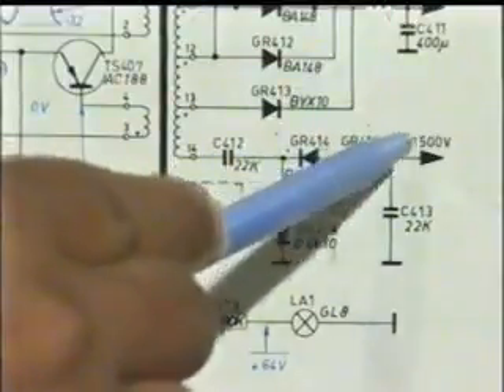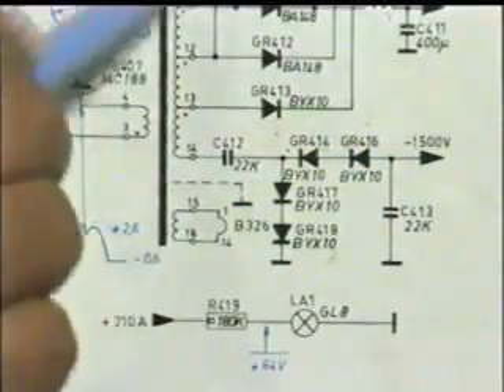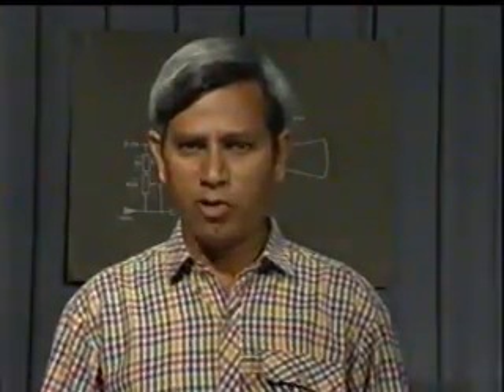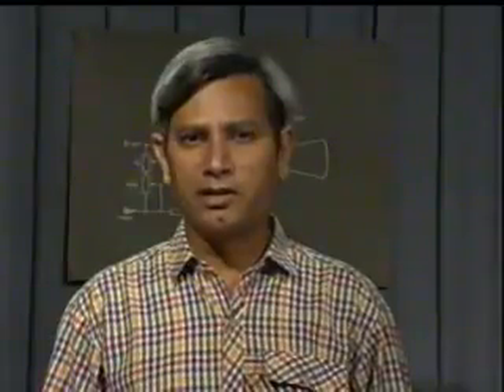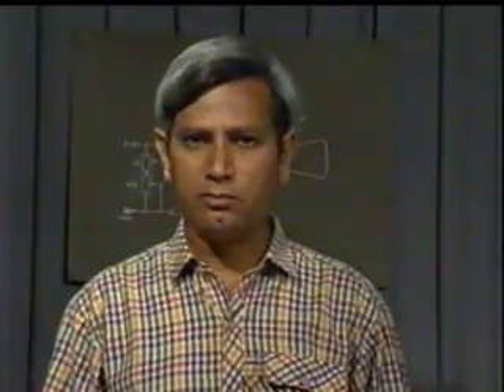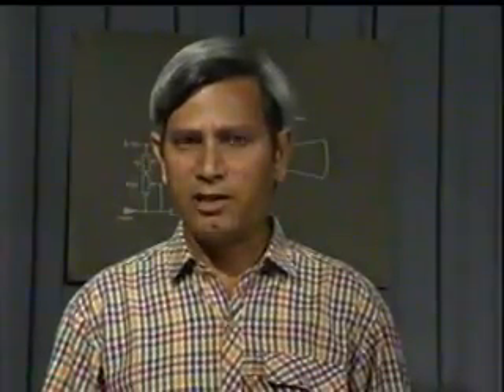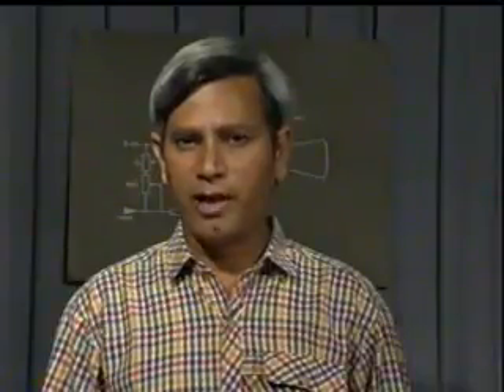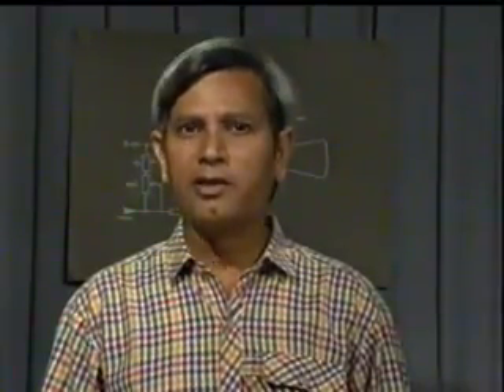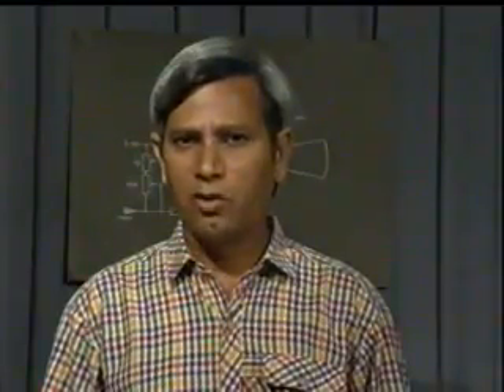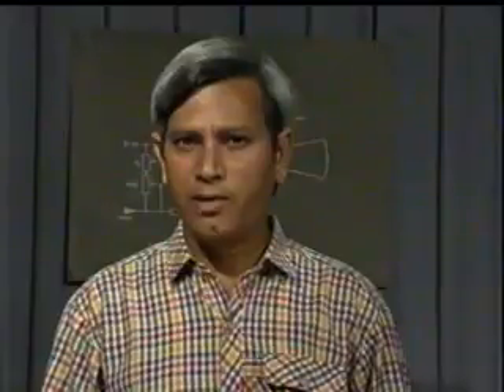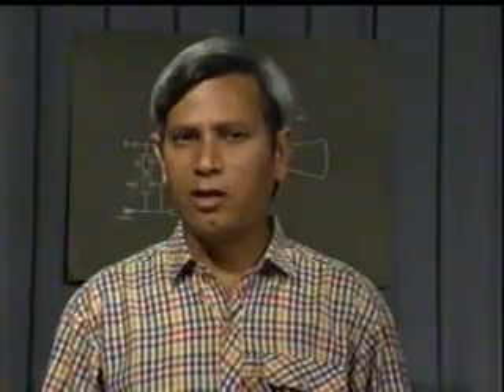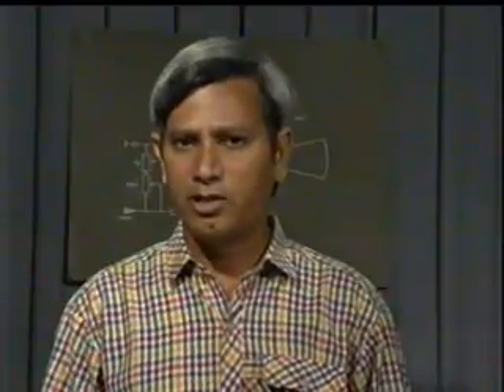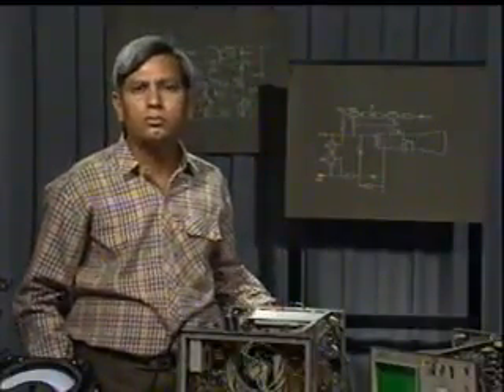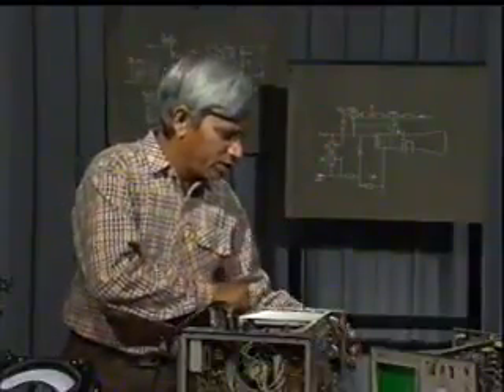Here the high voltage has been taken from the same transformer. If the low voltages of the power supply sections are okay, the next step is to check the high voltage. The high voltage has been generated from the same power supply using a multiplier. If we are not getting the high voltage, which is minus 1500 volt, the suspected components are either multiplying diodes or capacitors. To check the EHT, first switch off the CRO and see the voltage at the EHT terminal.